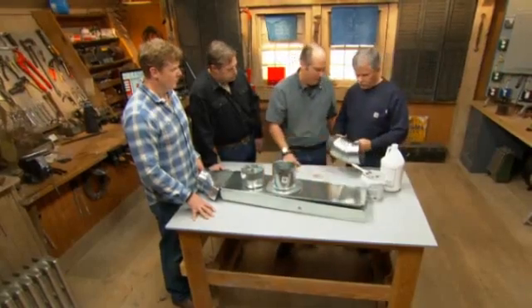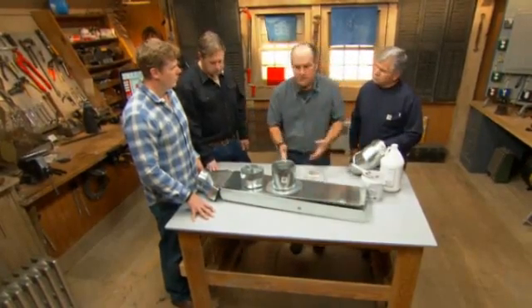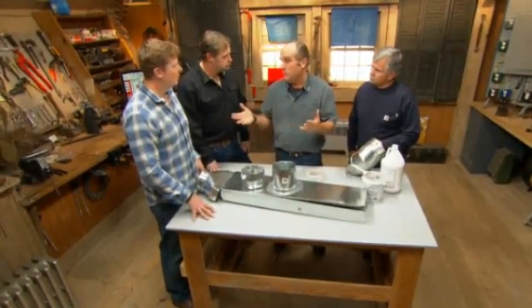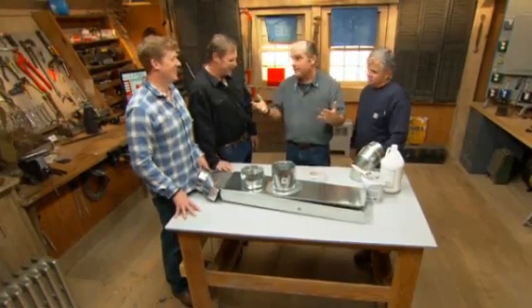Here's another version of the same thing — it has double-stick tape on the backside, so it makes a nice tight seal. What about all these swivel elbows? The swivels are never airtight, so you're going to have to use a mastic or foil tape right here. The issue is we're losing 20, 30, 40 percent of the air that should be going into the living space for heating and cooling. We end up putting duct work where nobody really wants to go — the basement and the attic — so when you lose it there, you lose it. Something like this is perfect for a retrofit project. I've never seen a better solution for fixing the duct work.